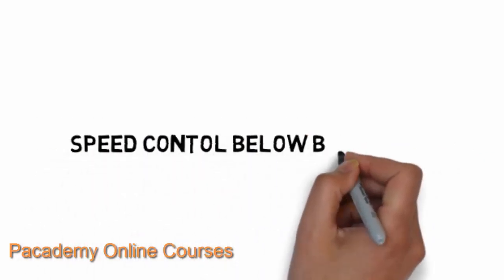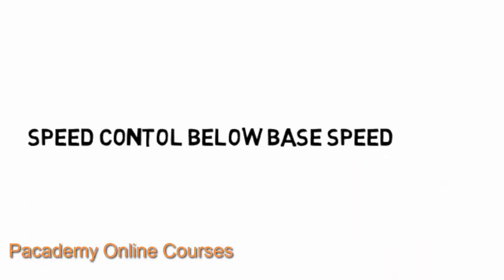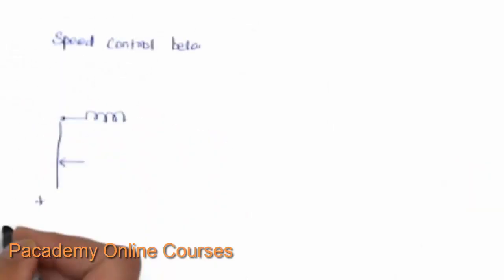The next type of control is for series motors. For achieving speed below the rated base speed, when two series motors are connected in series across the supply voltage, the voltage available across each motor is half the supply voltage (V/2). By reducing the voltage available across the terminals, speed below the rated speed can be achieved, since speed is directly proportional to voltage.